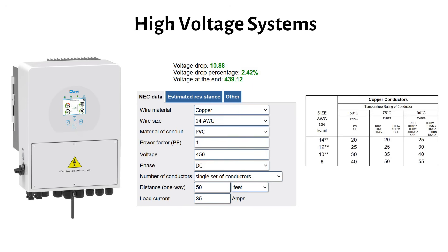If we look at the current table, 14 gauge is only rated for about 25 amps. And we need 35 amps. That's why we always do the final safety check to see if the calculated cable is not below the minimum current rating. In this case, we would have to move up to a 10 gauge PV cable rated for 40 amps.